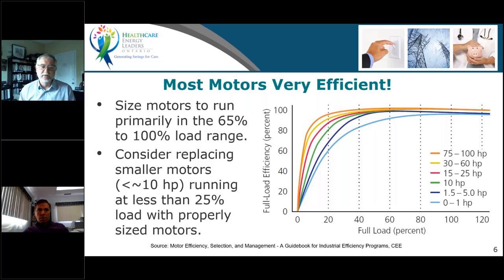Another one to watch out for is if you've got an old motor driving a centrifugal pump and you move to an energy efficient or premium efficiency motor. Today you would be buying a premium efficiency motor. You may just find that motor spins faster afterwards. Due to the laws that I'm going to show you in a few slides, the pump affinity laws, you're now going to be consuming more power. So a 1% speed increase on the shaft of that pump can actually create a requirement for 3.5% more power. And if you're only going to get 2 or 3% efficiency improvement out of that new motor, guess what? You are now back where you started.